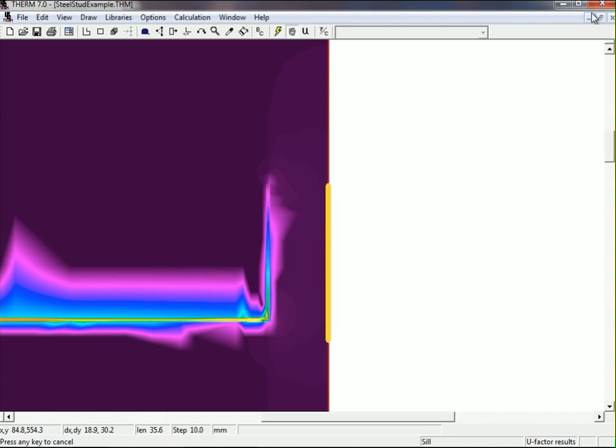You see a lot of the heat flux is going, of course, through the metal stud, which is the short circuit which breaks through the insulation. And you see that the area under condensation pretty much matches the effect of this stud. So you see it's right around where the center part of the stud touches the wall is where you're going to get the lowest temperatures.